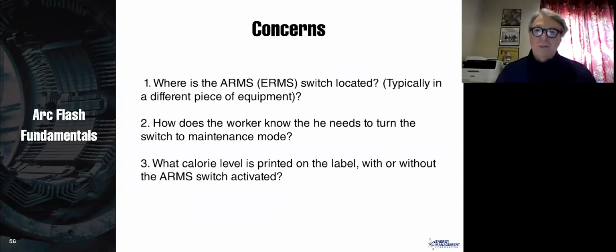Now here's my concerns, and I struggle with this a lot. Where is that ARMS switch located? Well, typically the ARMS switch is going to be located in another piece of equipment. So if you're working on a motor control center, the arc flash rating on that motor control center is going to be the arc flash coming into the motor control center, because at least in the main breaker section, if you have an arc flash, it could cause an arc on the primary terminals of that main breaker, and therefore the thing that's going to interrupt that is going to be the piece of equipment that feeds that motor control center. So where is that? Typically in another location, in another piece of equipment.